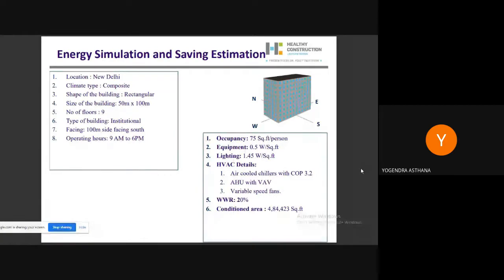So here we are taking an example of a building located in Delhi, and the shape of the building is rectangular, 50 meter by 100 meter. Number of floors are 9. It is an institutional building, and it is south facing. The 100 meter side is facing south, and it will be used from 9 to 6. As per ECBC guideline, we have a full day 24-hour use building or a daytime use building, so the energy requirement will be based on that.